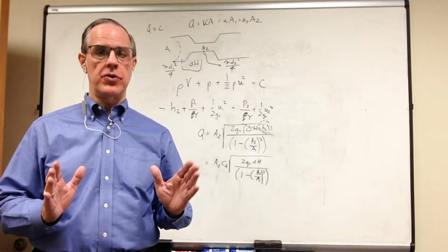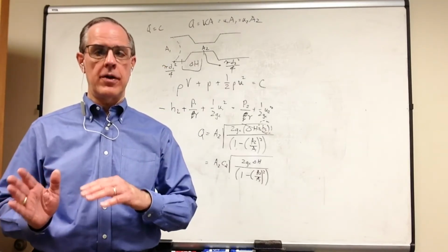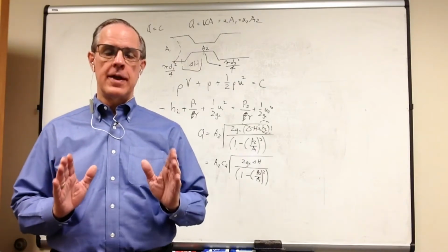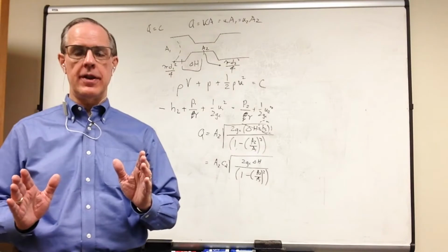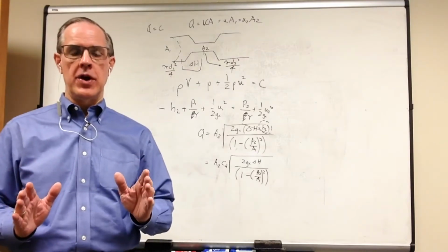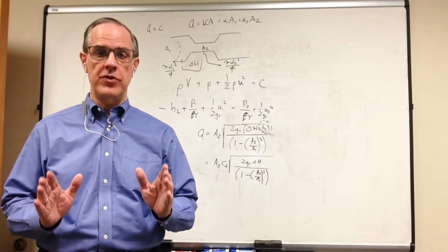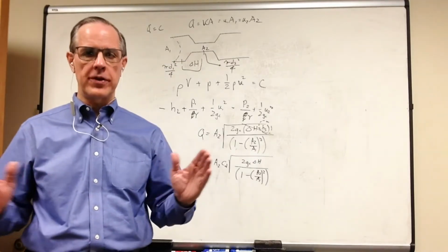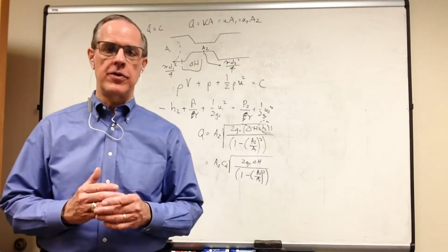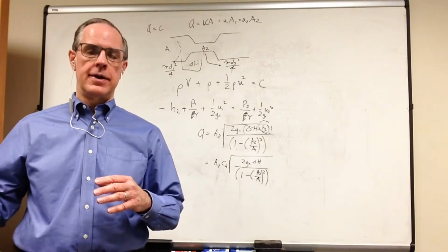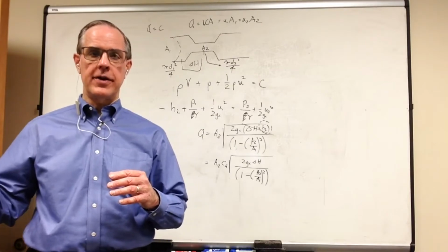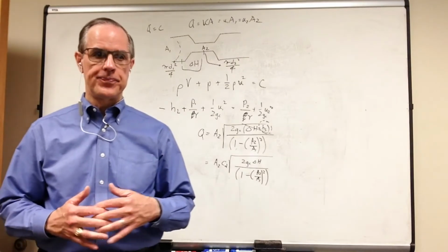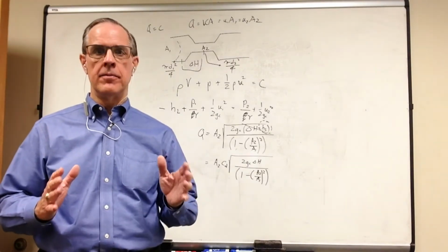Now, however, we're going to turn to the flip side of that, which are minor losses. The existence of that HL assumes that there's some kind of loss in that flow meter. While we're measuring the flow, we actually use energy, which is true. Which is why, from an energy standpoint, if you've got the real estate to do it, you're better off using a high CD flow meter like a Venturi, as opposed to a low CD meter like the orifice.